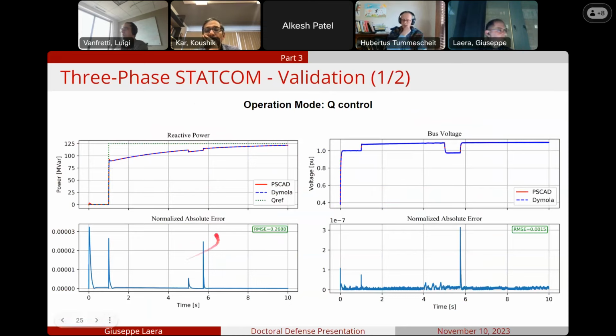So we were talking about the validation of this model. After describing the step in the reactive power at 1 second and the presence of the three-phase fault at 5 seconds, we can see that after an initial variation at the beginning of the reactive power injected by the STATCOM to reach an equilibrium point, the measured reactive power stays at 0 megavar until the step is set at 125 at 1 second. Then the reactive power injected by the STATCOM increases, trying to track the new reference value. Then we see a drop that is due to the three-phase fault applied to the bus where the STATCOM is connected.